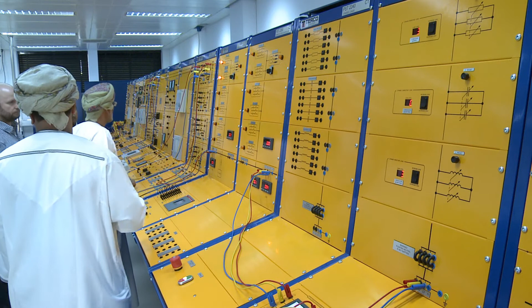There's a manual, a complete manual on all of the features of this particular unit. It takes about 2 days to go through and try all of the things. One of the switching schedules you can do is, just now we are beginning always at step 1, but if you have proper capacitor banks, you might want to use them all equally. So at the moment, this one will never get connected unless we have very, very bad power factor.